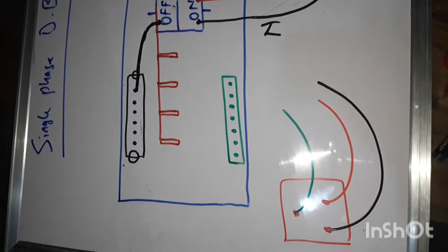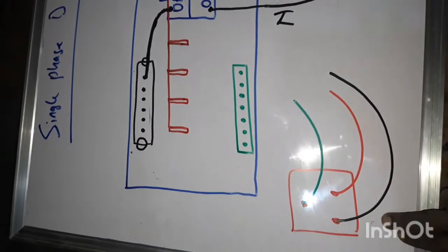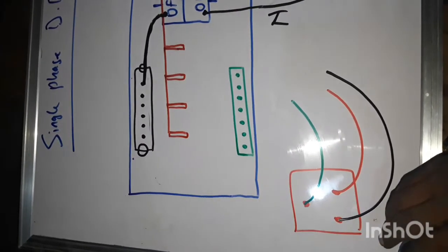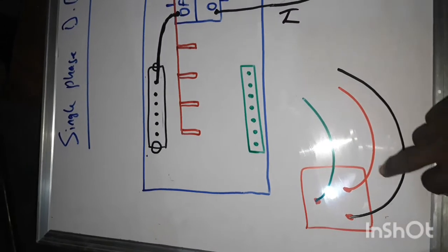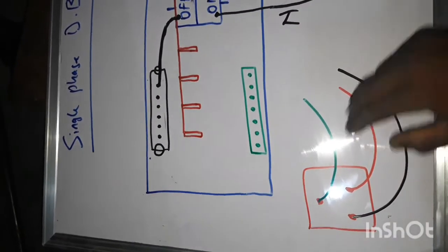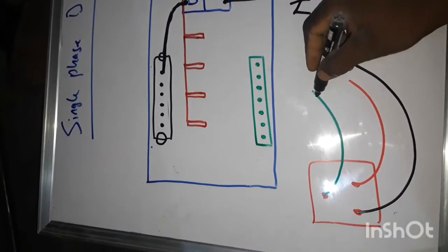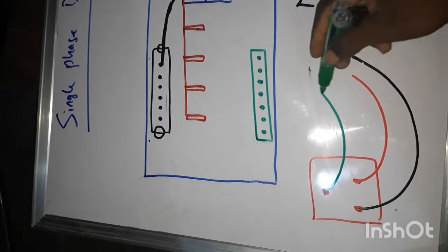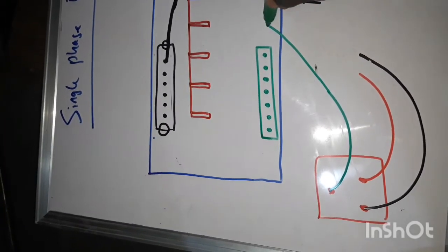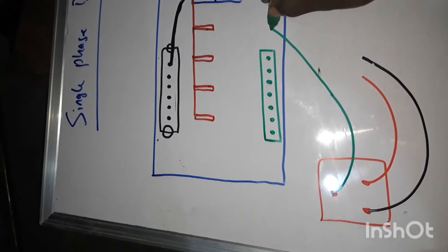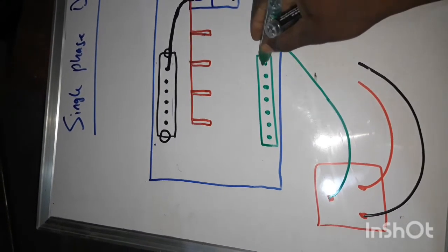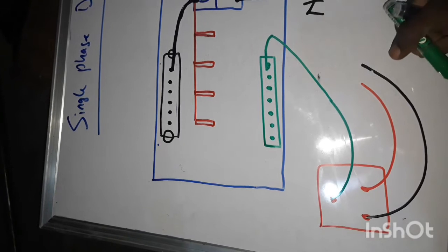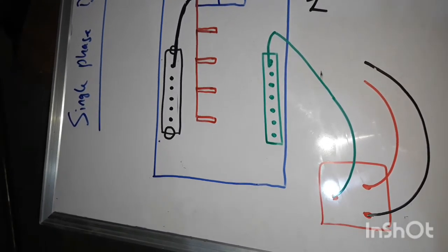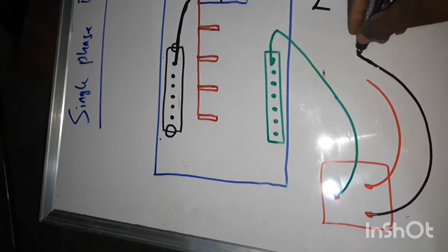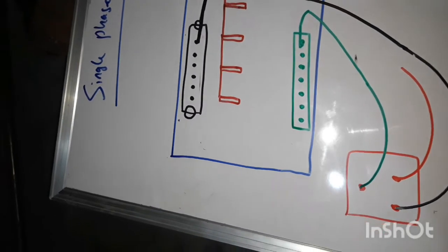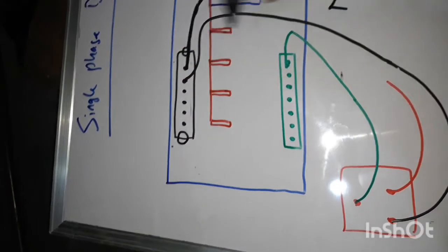your final sub-circuit. Let's assume this is your socket now. This is your socket, and you wired your socket with live, neutral, and the earth. So the three wires, once they enter into the distribution board, you already know that your earth wire is going to come to your earth terminal. Your neutral wire should be connected directly to your neutral bus bar.